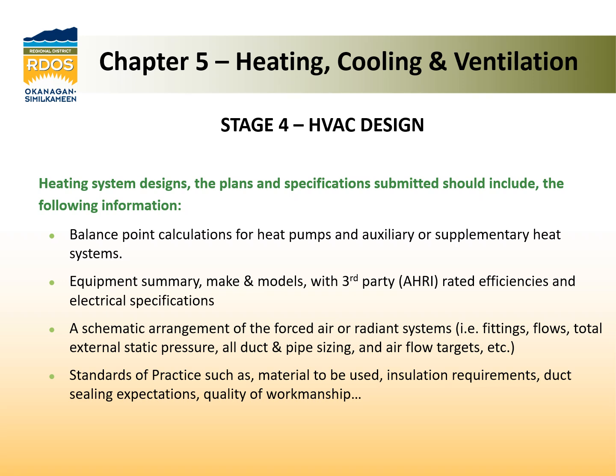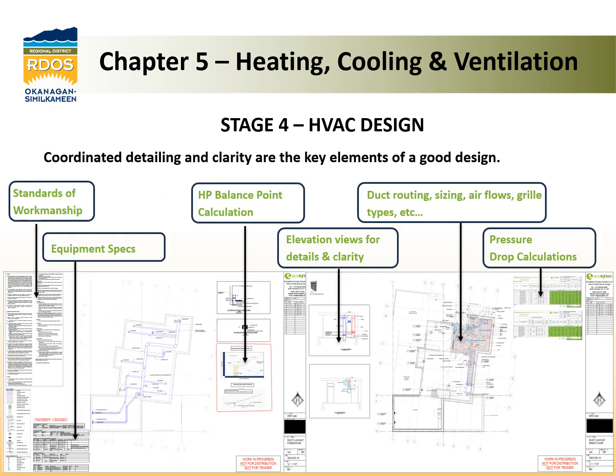such as balance point calculations for heat pumps and auxiliary or supplementary heat systems, equipment summary, make and models with third-party rated efficiencies and electrical specifications, a schematic arrangement of the forced air or radiant systems. For example, fittings, flows, total external static pressure, all duct and pipe sizing and airflow targets. Standards of practice, such as material to be used, insulation requirements, duct sealing expectations, and quality of workmanship. Here's what those basic components of an HVAC design would look like. Design should be detailed and comprehensive enough so that it's crystal clear what goes in and how it all fits together.